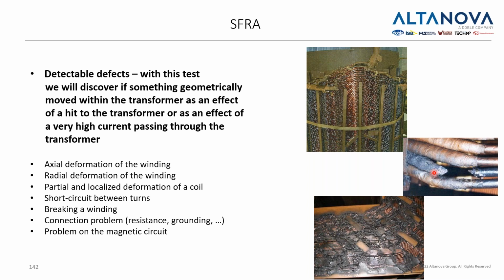And this test is always done in a factory, and then the transformer is transported to the location, and then that test is repeated. If we get the same result, then it means nothing hit the transformer. But you can also do this test after there has been a high current fault near the transformer, because the high current passing through the transformer may cause a big electromagnetic field which can physically move the coil.